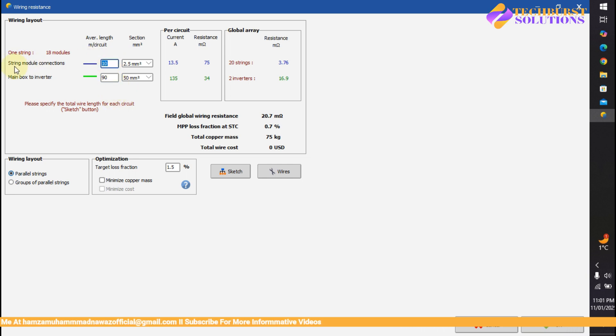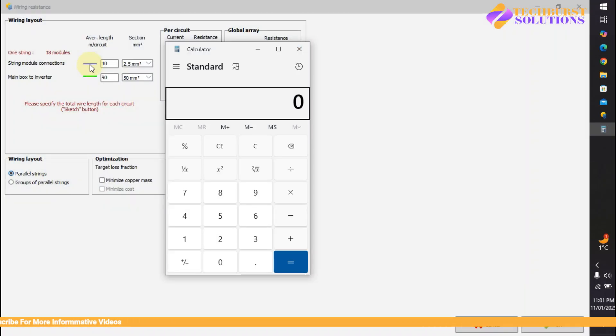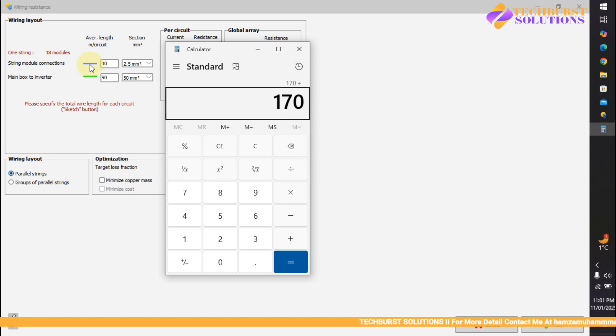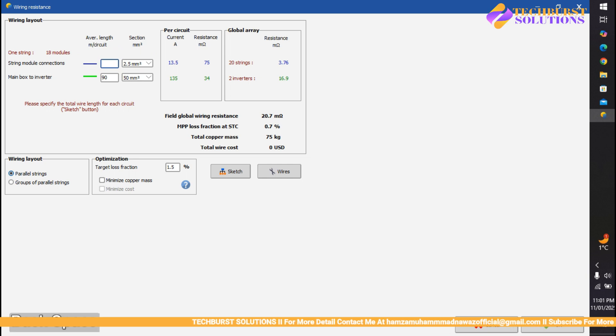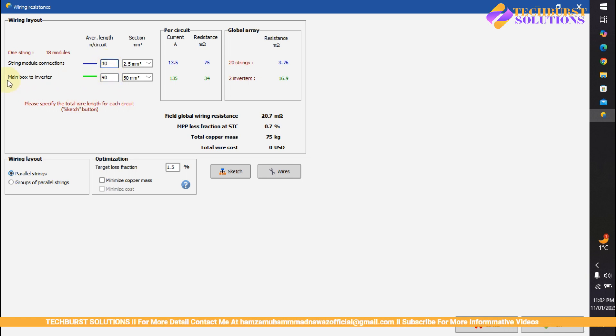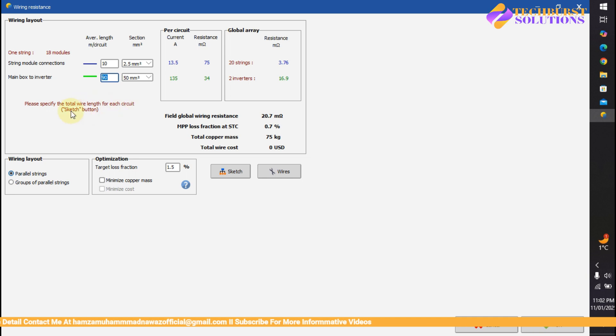For string module connection, let me give you an example. Suppose you have multiple module string connectors of different lengths — 10 meters, 30 meters, 50 meters, 60 meters, and 20 meters. Adding them gives 170 meters. In my case with five strings, I divide 170 by 5 to get an average of 34 meters. You add that average value for the string wires, and main box to inverter is 90 meters.